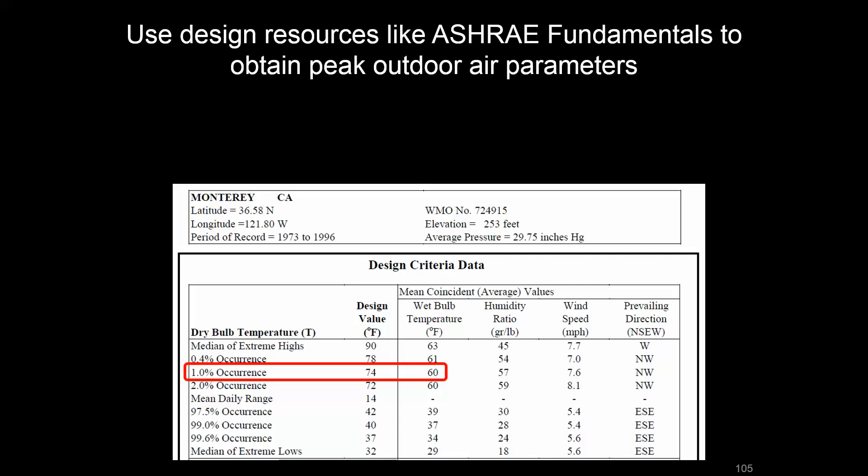Where you're going to get most of your, 99% of your days are going to be that hot or less. And the 99% occurrence is actually the, on the flip side, the heating condition that is going to be not the absolute worst case, but what you size your equipment to.